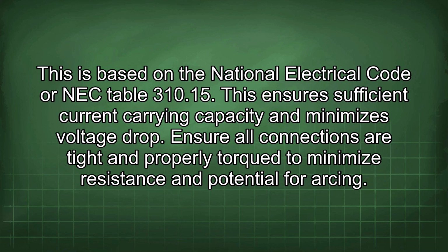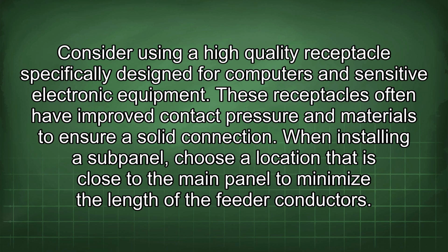Ensure all connections are tight and properly torqued to minimize resistance and potential for arcing. Consider using a high-quality receptacle specifically designed for computers and sensitive electronic equipment. These receptacles often have improved contact pressure and materials to ensure a solid connection.